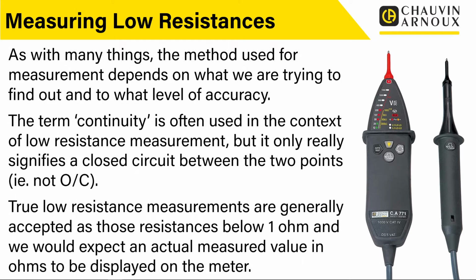So as with many things, the methods used for measurement depend on what we're trying to find out and to what level of accuracy. The term continuity is often used in the context of low resistance measurement, but it only really signifies a closed circuit between 2 points, i.e. that they're not open circuit. So it's great if we're looking for breaks in a wire, or we're looking to see which end of one plug's connected to which pin on another plug. We're doing a continuity measurement, but really it doesn't tell you a lot more than that. It certainly doesn't tell you about the quality of connections, deterioration or frayed cables or anything like that. It is just literally telling you that between the 2 points there is an electrical connection, there is continuity.